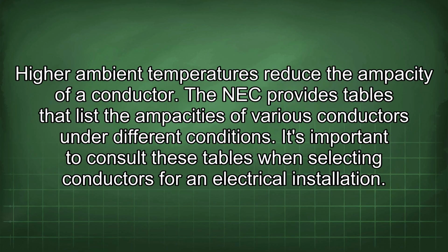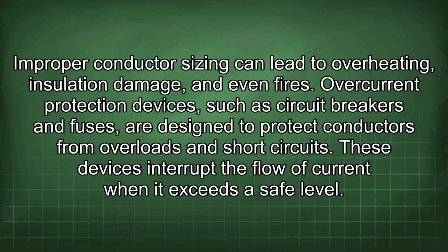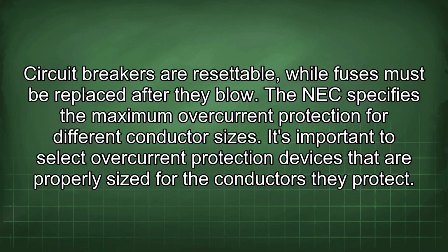Higher ambient temperatures reduce the ampacity of a conductor. The NEC provides tables that list the ampacities of various conductors under different conditions. It's important to consult these tables when selecting conductors for an electrical installation. Improper conductor sizing can lead to overheating, insulation damage, and even fires. Overcurrent protection devices, such as circuit breakers and fuses, are designed to protect conductors from overloads and short circuits. These devices interrupt the flow of current when it exceeds a safe level. Circuit breakers are resettable, while fuses must be replaced after they blow.